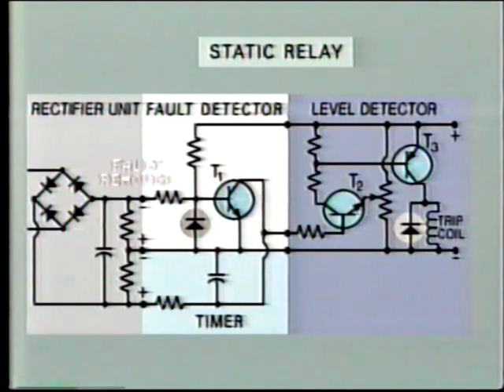When the fault is removed, the fault detector immediately goes back to the conducting state and discharges the capacitor, thereby resetting the relay. The actual time delay and inverse time characteristic can be varied by changing the timing circuit. For an instantaneous unit, there would be no timing capacitor. Instead, the current will flow directly to the triggering transistor.